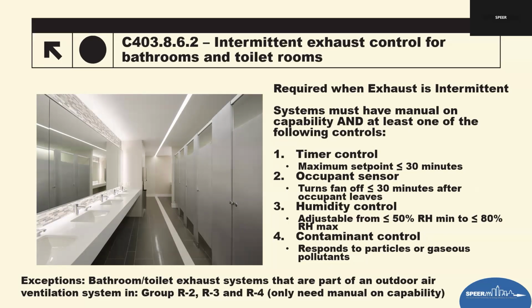This ensures the system only runs when needed and avoids unnecessary energy use from continuous operations. So 1, a timer control less than or equal to 30 minutes. So a timer can be used. It must be limited to no more than 30 minutes. This prevents the fan from running excessively. Occupant sensor shutoff is less than or equal to 30 minutes. So once the person leaves, it will shut off. Humidity control, it's going to be between 50 to 80% relative humidity if you have a humidity sensor. So minimum set point must not be greater than 50%. The max cannot be greater than 80%. This prevents the user from disabling the fan by choosing an unreasonably high humidity setting.